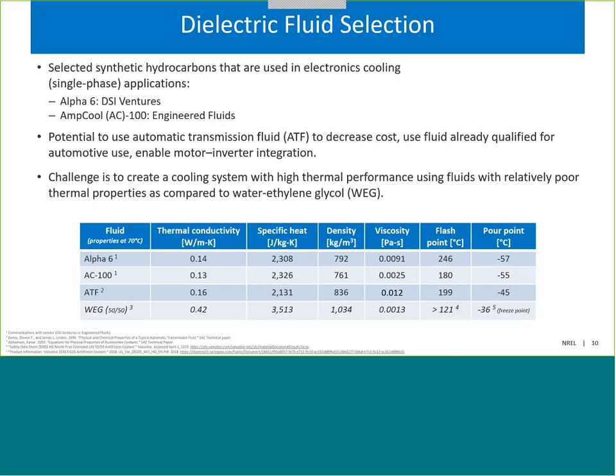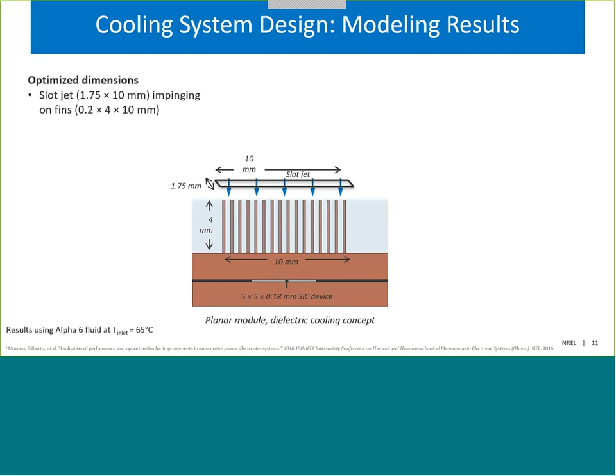This slide describes the cooling system design to cool one device. We did a lot of modeling work to optimize the size of the slot jet and also of the fins. The final design used a slot jet with dimensions of 1.75 millimeters by 10 millimeters. That jet impinged on fins that were 0.2 millimeters in thickness, 4 millimeters in height, and 10 millimeters in length. That design achieved an overall heat transfer coefficient of about 17,300 watts per meter squared degree K at a relatively low jet velocity of about 0.3 meters per second. This is a relatively high performance considering we're using a fluid with relatively poor properties.